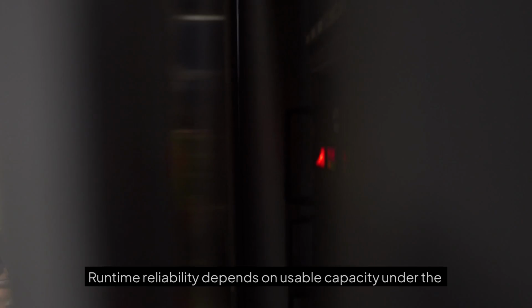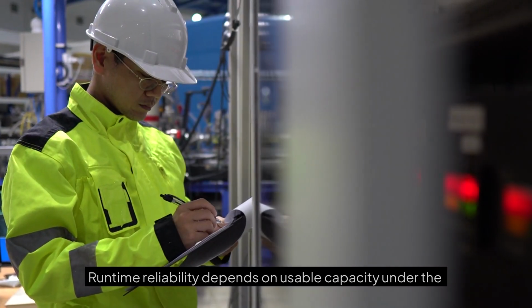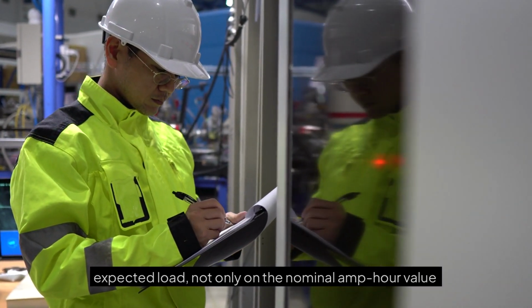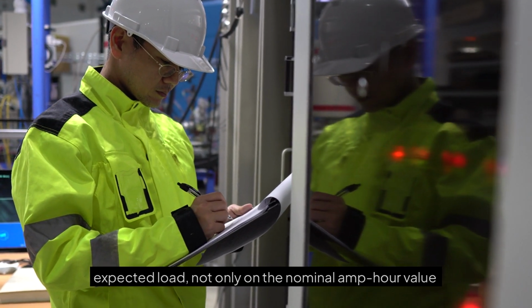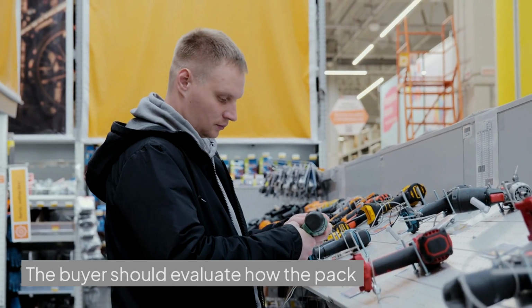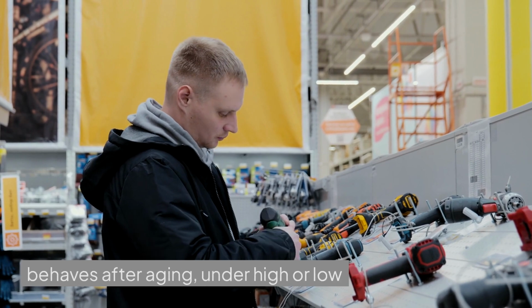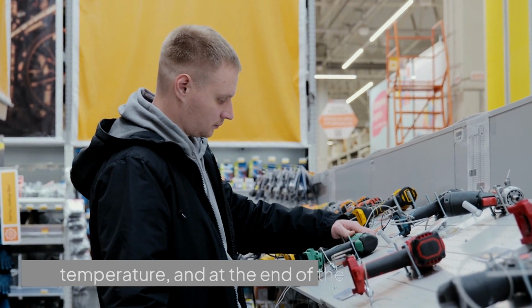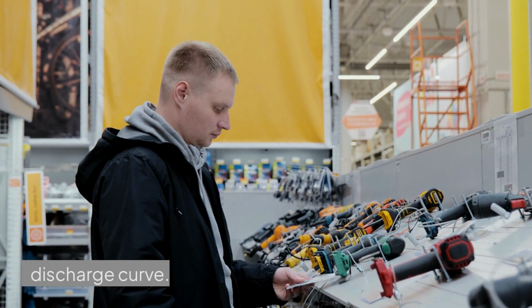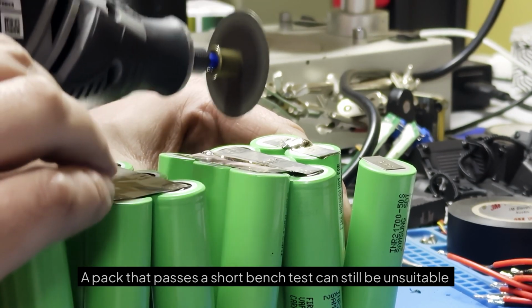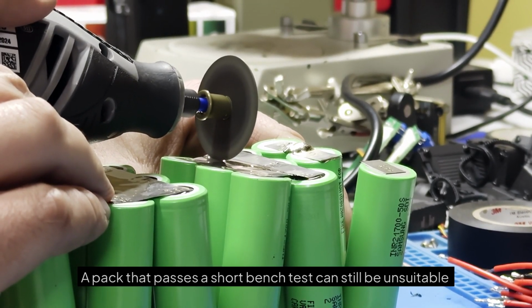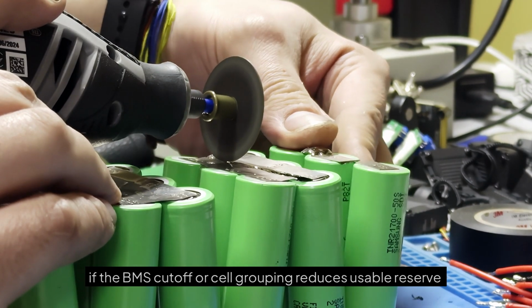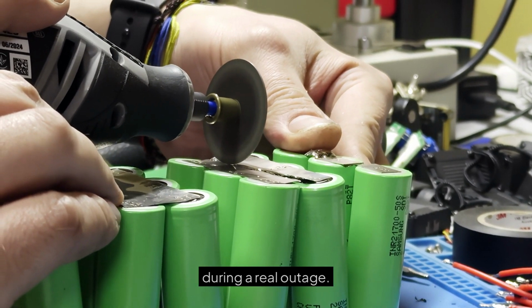During power failure, runtime reliability depends on usable capacity under the expected load, not only on the nominal amp-hour value printed on a datasheet. The buyer should evaluate how the pack behaves after aging, under high or low temperature, and at the end of the discharge curve. A pack that passes a short bench test can still be unsuitable if the BMS cutoff or cell grouping reduces usable reserve during a real outage.